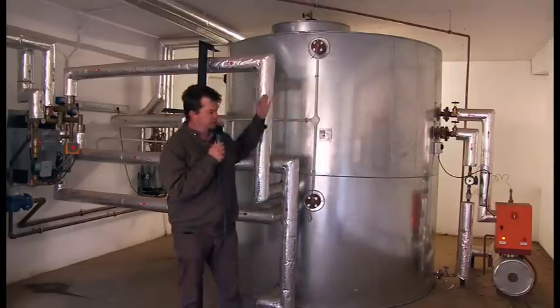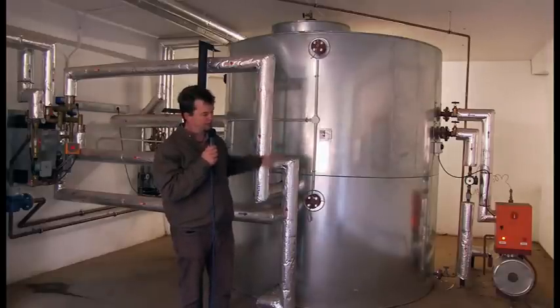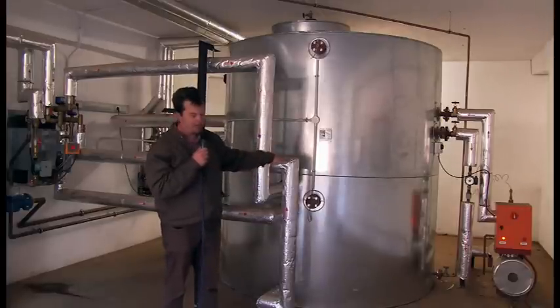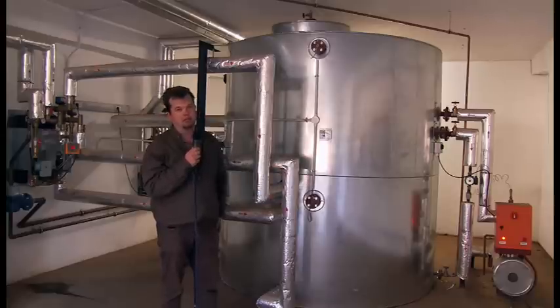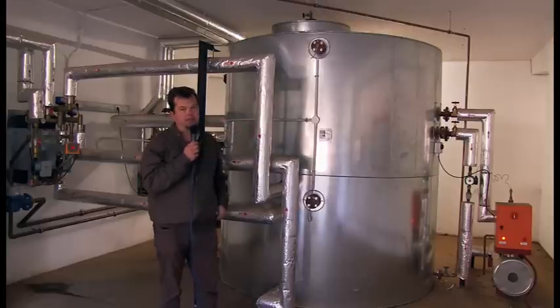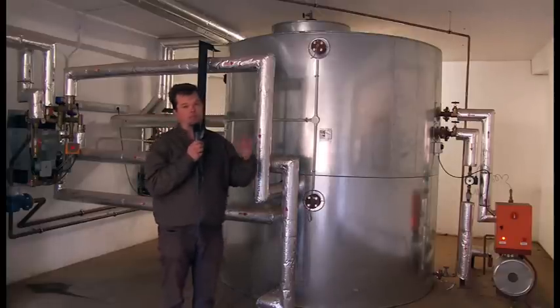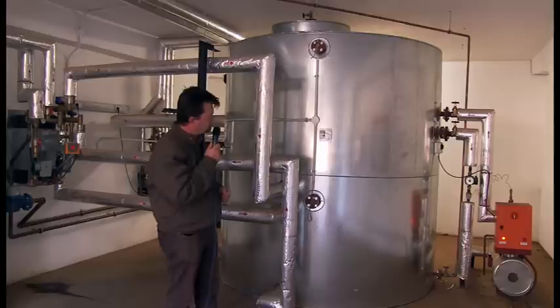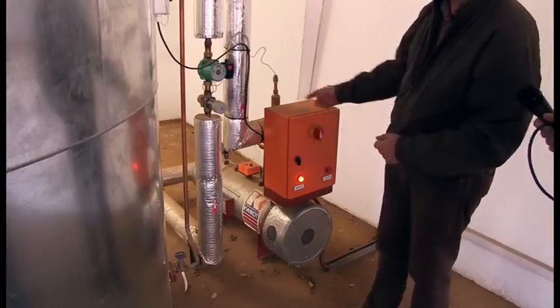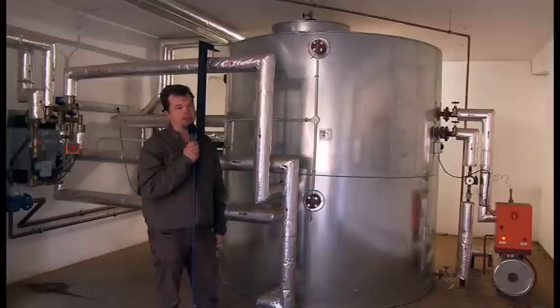All the pipes, as you can see, are well insulated — about the thickness of the pipe itself. Behind me we have the storage tank. It's a vertical tank, promoting the idea of hot water at the top and stratifying, with very thick insulation. All the pipes penetrate the tank at the lower level, and this is to avoid heat leakage at the top of the tank. The tank itself is insulated with about 120 millimeters of rock wool, which is far beyond the standard specification. On my left-hand side you see a backup resistive element, only heating the top third, for periods of extended cloudy weather.